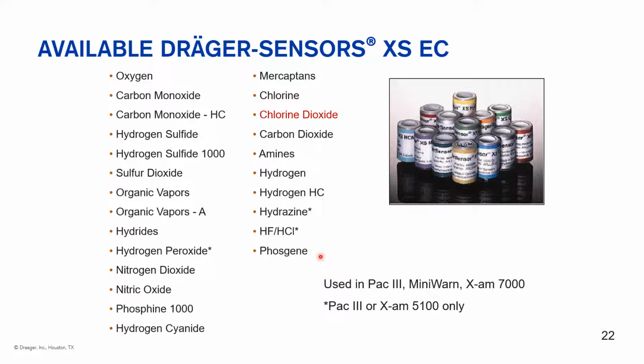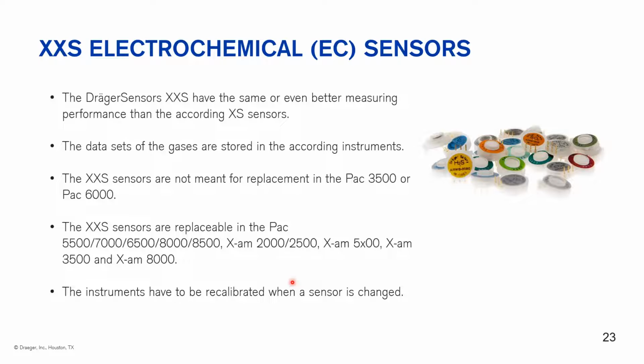So, sensors we have available: we have quite a number of our sensors available in the XS series. However, most of the development is going to our new XXS sensors. The XXS sensors, it's hard to say, but basically have better response time and better performance than a lot of our XS series sensors. And these are not smart sensors, so all the data is actually stored on the instrument. And of course, they are replaceable in most of the instruments that we do offer. But when you do change a sensor out from one instrument to another, it will have to be recalibrated.